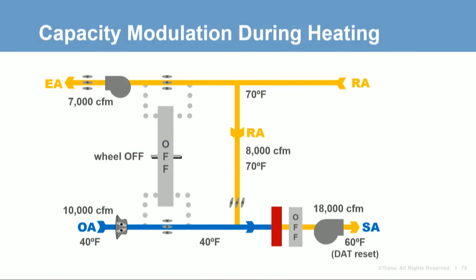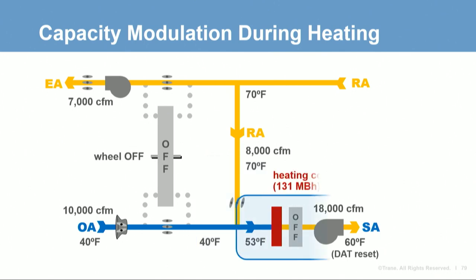If we turn the device off instead, with no heat recovery the mixed air temperature is 53 degrees, and the heating coil must activate to warm the air 7 degrees to the 60-degree set point — wasting new energy to heat the air. The right answer is to have some way to limit the capacity of the energy recovery device so it doesn't overheat the air. In this example with the wheel, the exhaust side bypass dampers are modulated partially open.